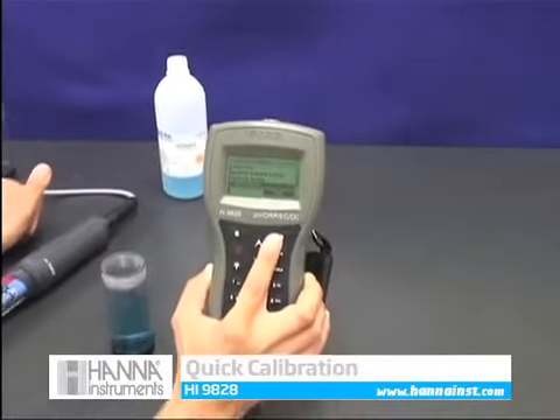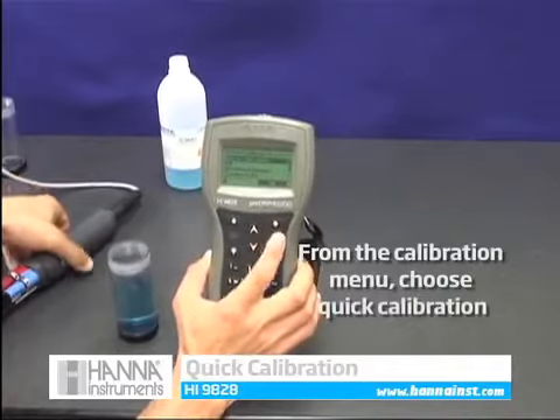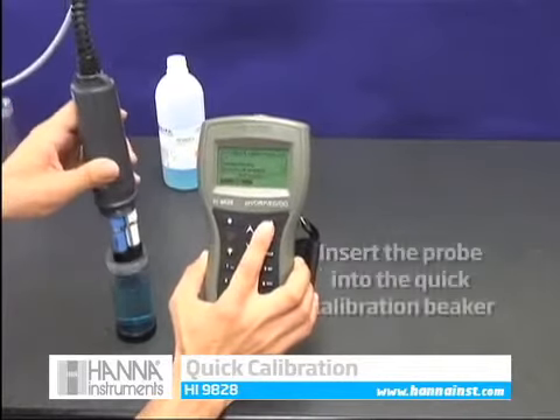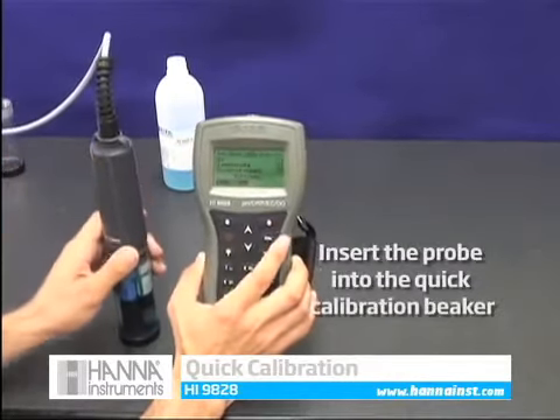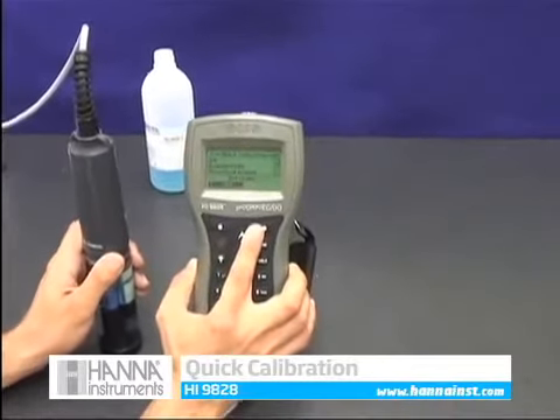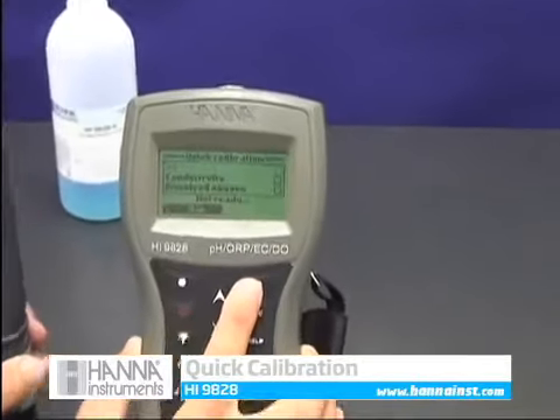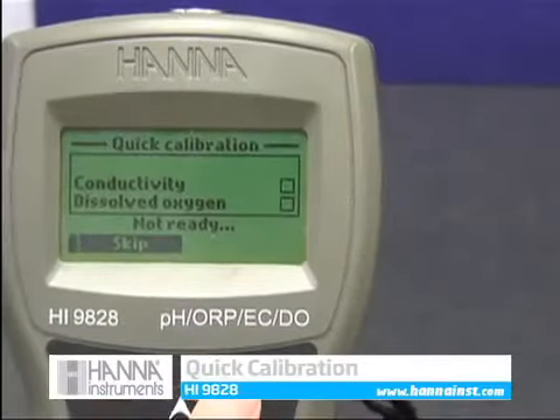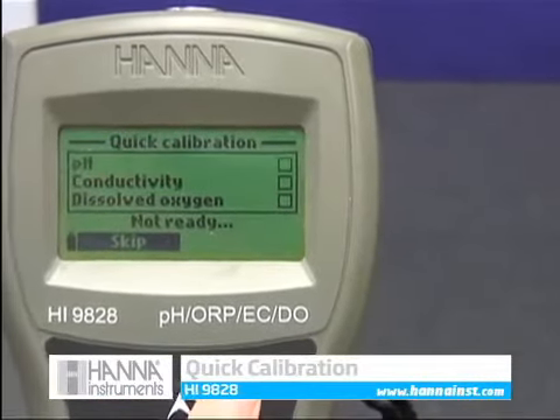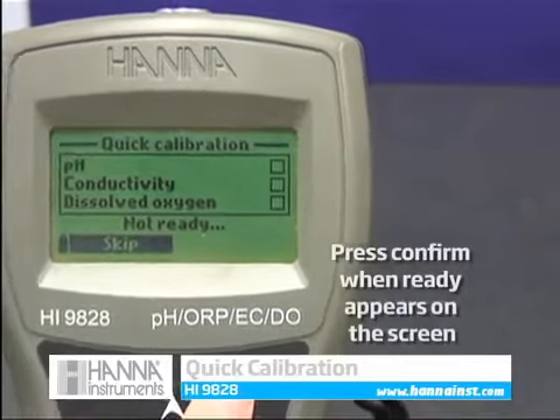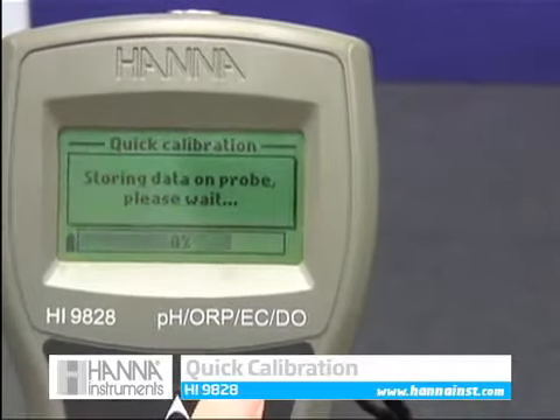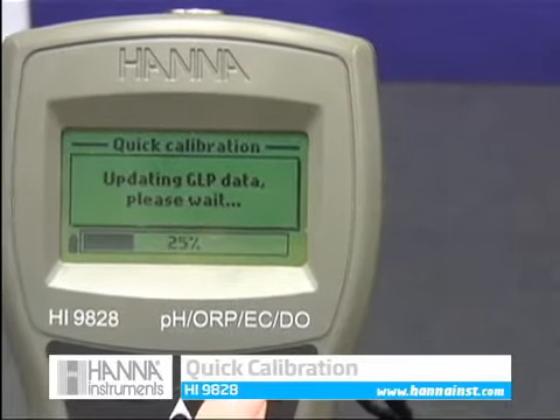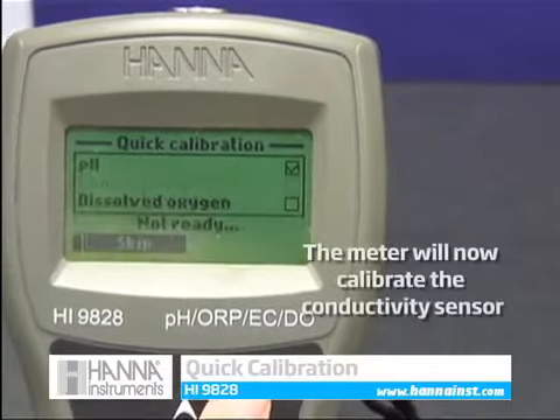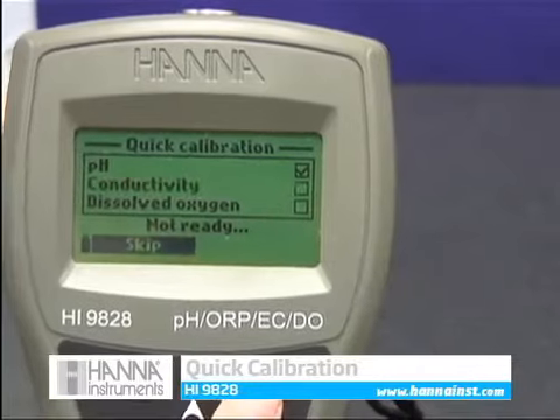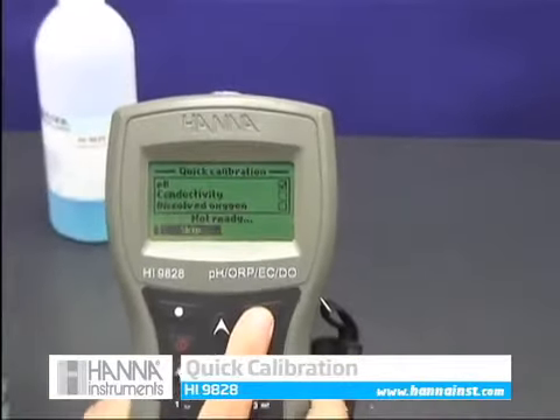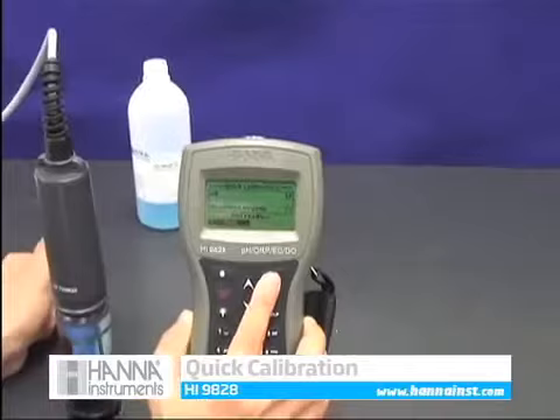Calibration is simple with our Quick Calibration feature. From the main menu, choose Calibration, then Quick Calibration. Insert the probe into the Quick Calibration beaker, and the meter will begin to calibrate for pH. When Ready appears on the screen, press Confirm, and the meter will store the calibration data and update GLP data. The meter will automatically begin to calibrate for conductivity. Once again, press Confirm when Ready appears on the screen to store the calibration and GLP data.